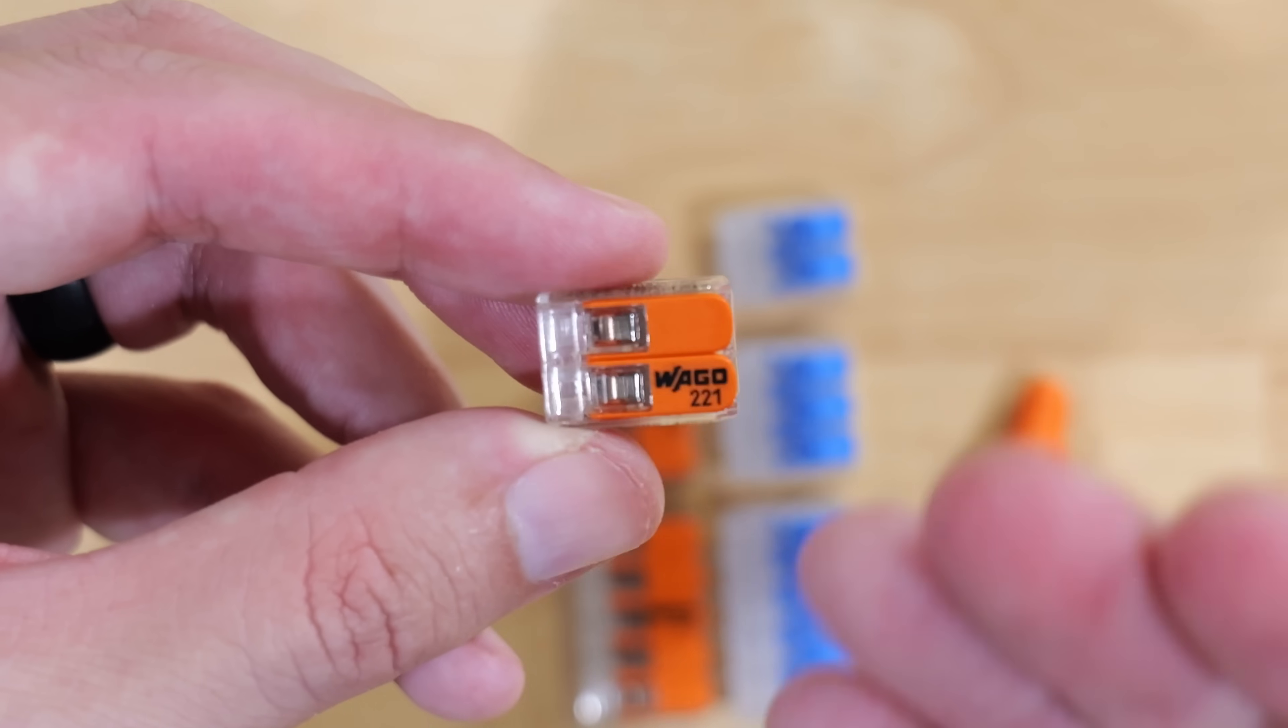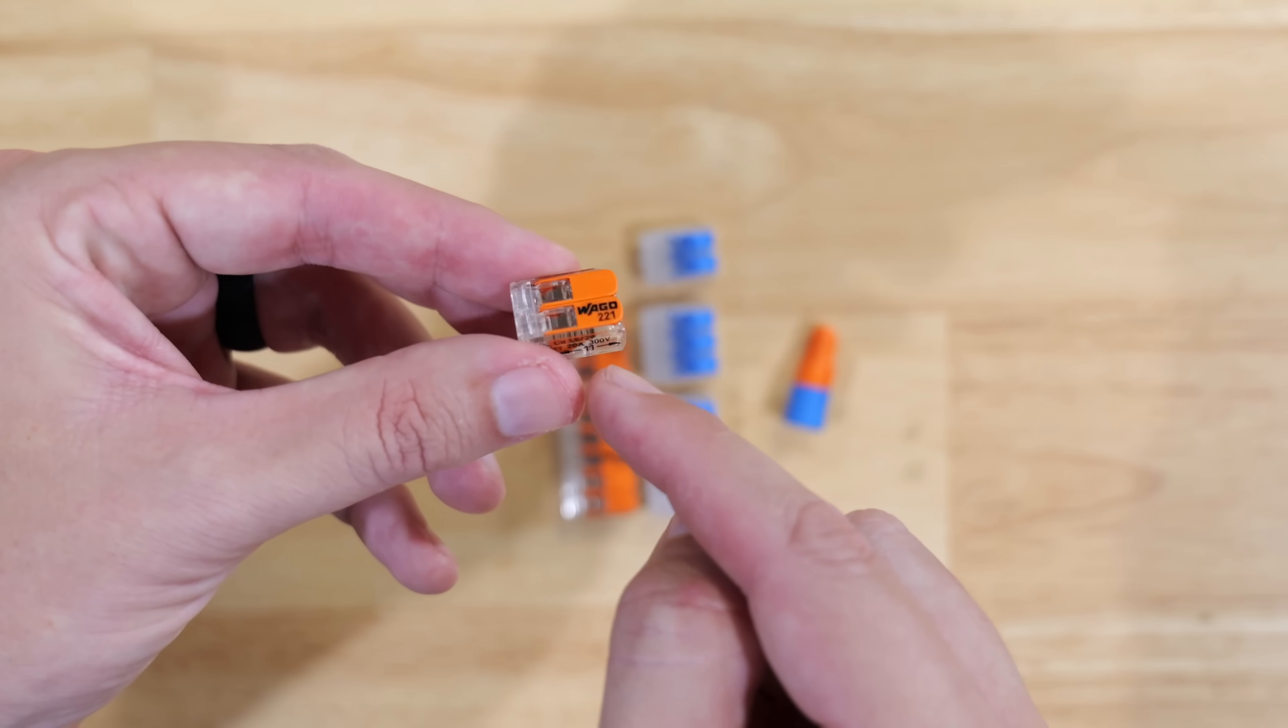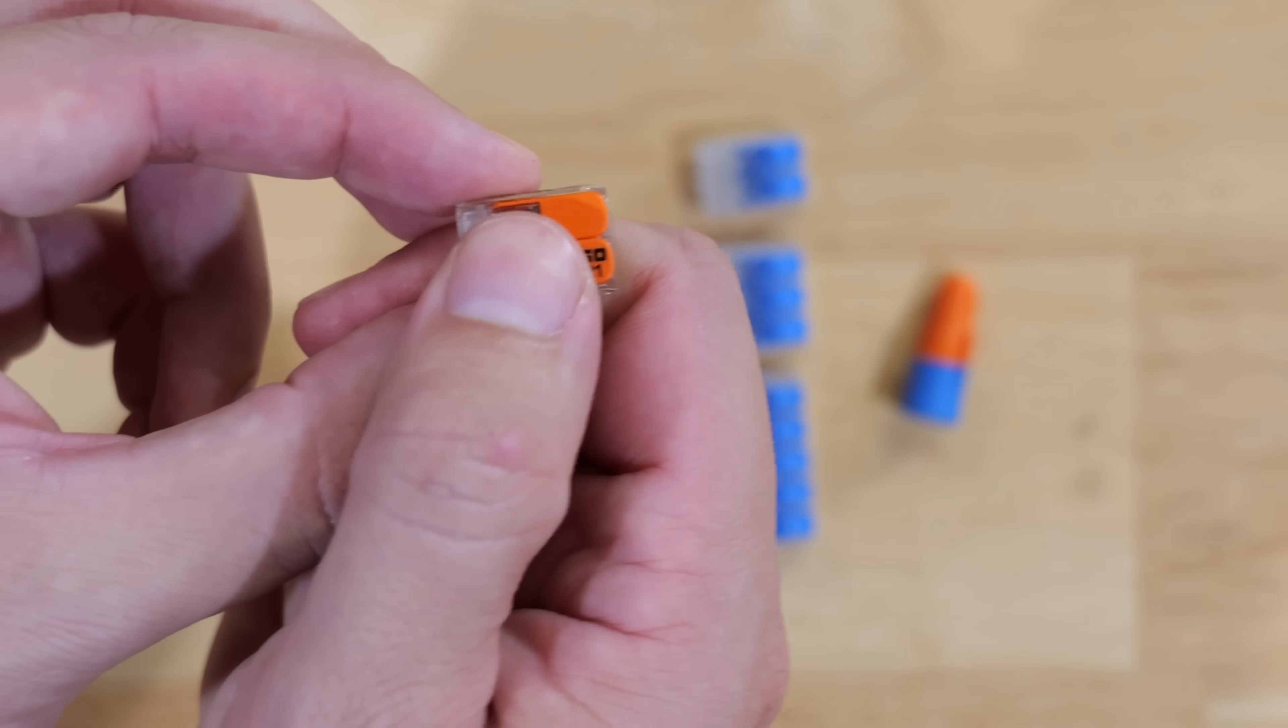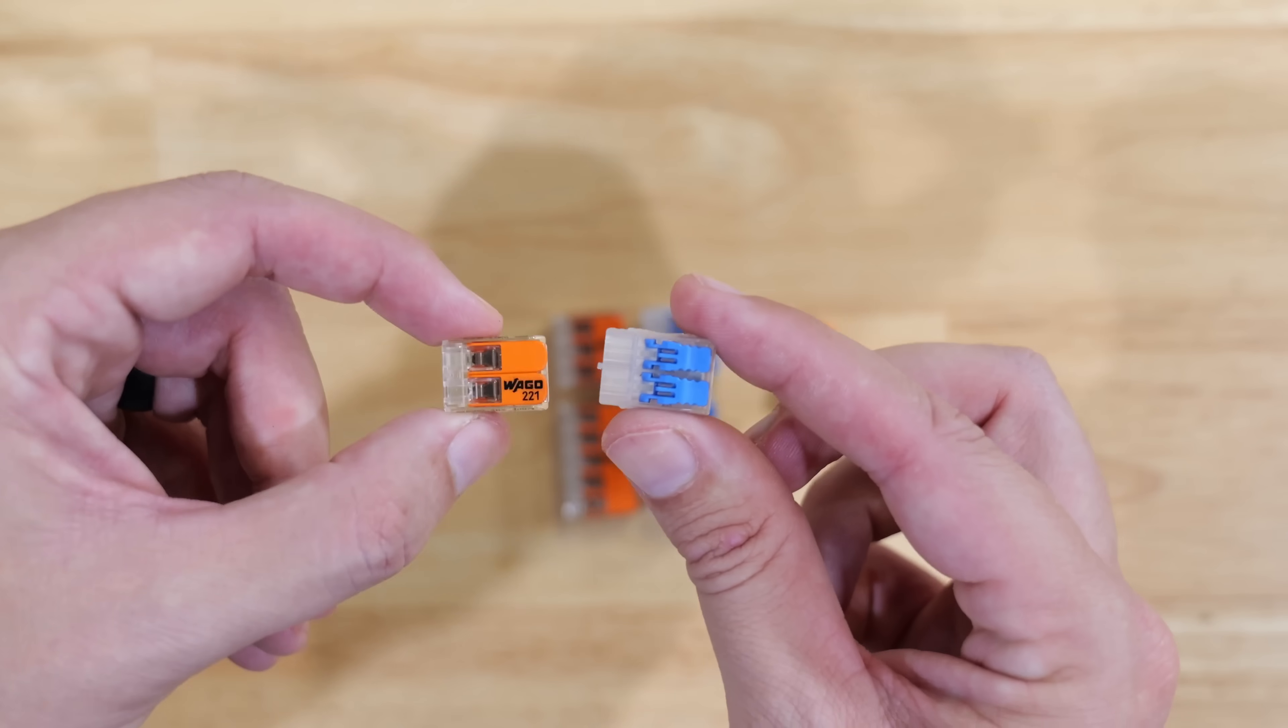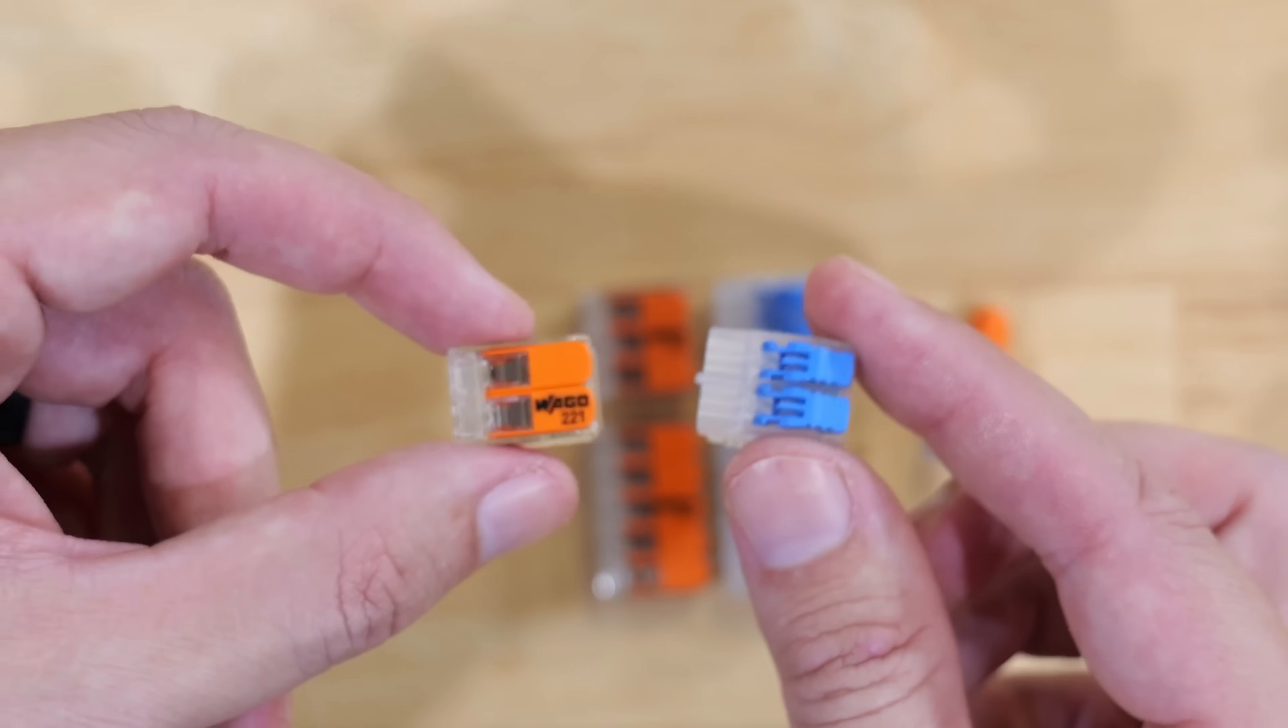When we go back to the WAGO here, it's really on the installer. It's the installer's fault if this was to get flipped up. A couple of things that you can do to make sure that doesn't happen: you could take a little piece of electrical tape and wrap it around the lever so they can't be flipped up, or what I tend to do is when I go to push these into the back of the box, I actually put my thumb over those levers. Until I get those wires and the connector seated where I want it in that box, I make sure that I keep my thumb on those levers so they cannot be opened at all.